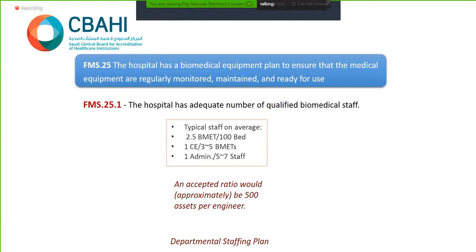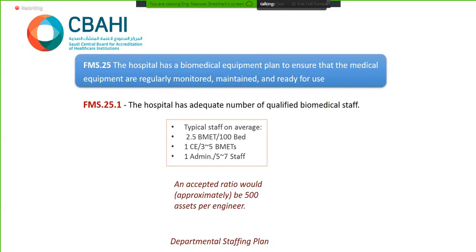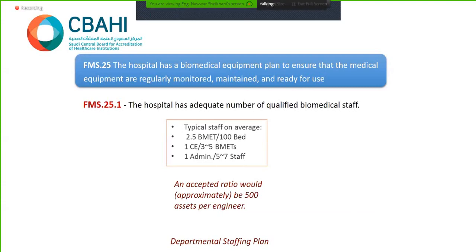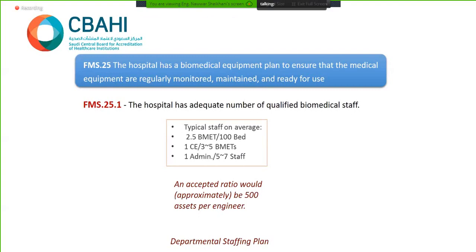So I mentioned two references here. Staffing on average is 2.5 technicians per 100 beds, so this reference is either per bed or per asset/equipment. The first one: 2.5 biomedical technicians per 100 beds, one engineer per 3 to 5 technicians, and one administrator or secretary per 5 to 7 staff. You can also follow the other criteria, calculated per assets, where the ratio was 500 assets per engineer. Hopefully that's clear.